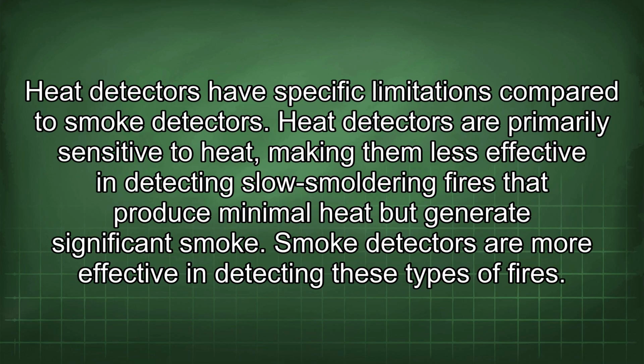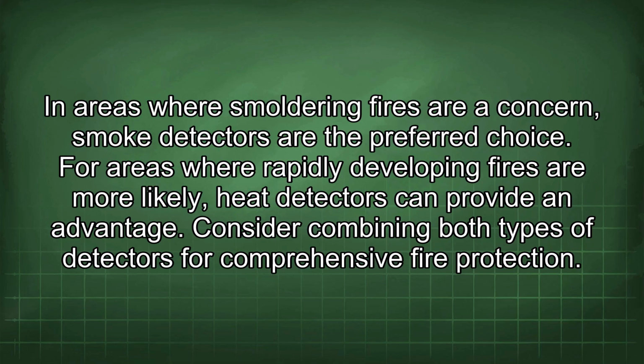Heat detectors have specific limitations compared to smoke detectors. Heat detectors are primarily sensitive to heat, making them less effective in detecting slow smoldering fires that produce minimal heat but generate significant smoke. Smoke detectors are more effective in detecting these types of fires. In areas where smoldering fires are a concern, smoke detectors are the preferred choice. For areas where rapidly developing fires are more likely, heat detectors can provide an advantage. Consider combining both types of detectors for comprehensive fire protection.